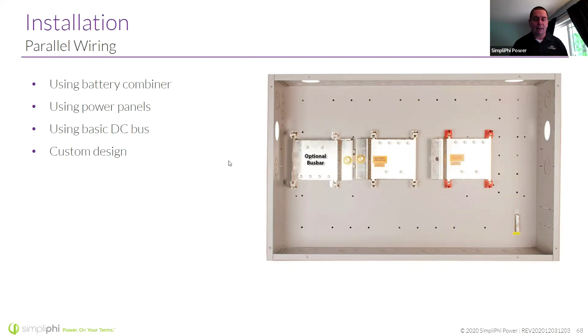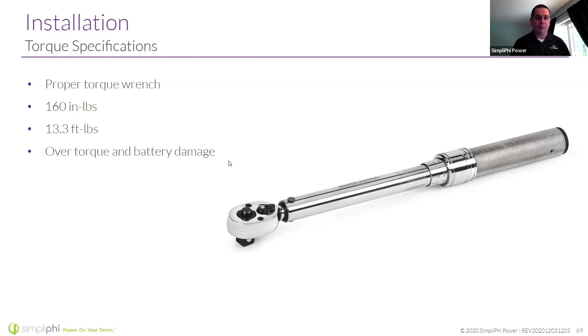Again, wiring in parallel - and always use a torque wrench. Don't hit our batteries with an impact driver, you can snap the terminals right off. 160 inch-pounds is probably not as tight as you'd expect, so a torque wrench will get you where you need. Take care of the batteries and they'll take care of you.